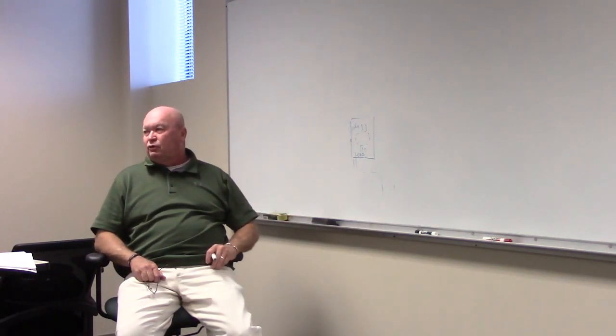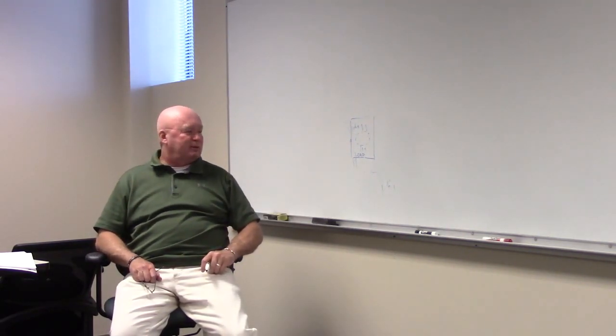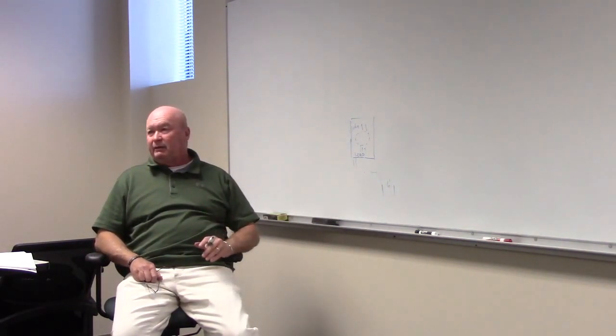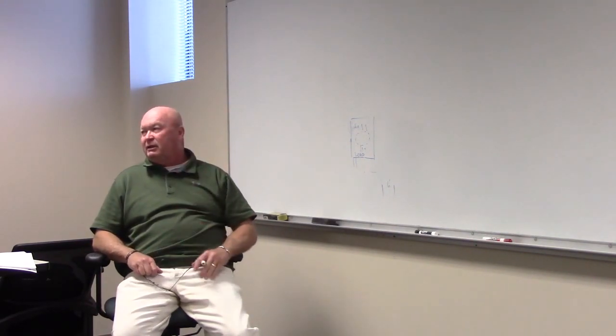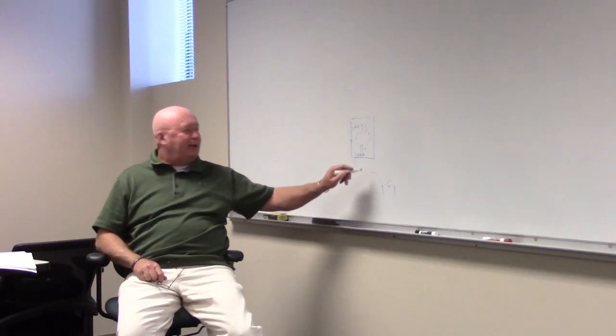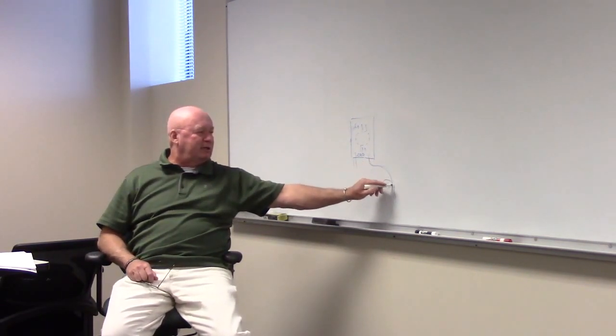City of Greenville or Greenville County, how many ground rods are required? 2. How many feet apart do they have to be? 6 foot, I think. I think it's 6 foot, minimum of 6 foot. They can be further, that's the minimum. Driving the ground rods straight down, they've got to be completely buried, correct? Can they be sticking up 6 inches? No. What if we ran into rock? What can we do? We've got a couple options. You can cut it. Oh, we can cut it, yeah, that's a good answer. What we're going to do is make this wire one continuous piece, aren't we? That's one thing. The other 2 things we could do, we could put it in at a 45.